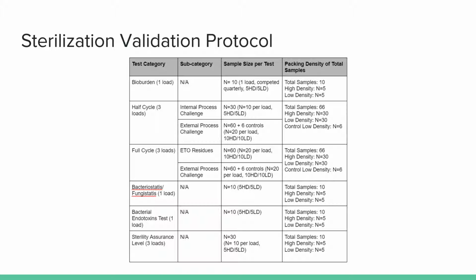3 loads of sterilization will be conducted for the major test to ensure that the sterilization process works reliably every time, and the devices will be tested in both a high-density packaging configuration, which is 5 devices per shipper, and a low-density configuration with only 1 device per shipper with dunnage to supplement. This will effectively test the worst-case scenarios for issues multiple times.